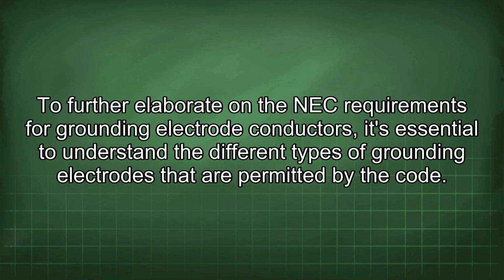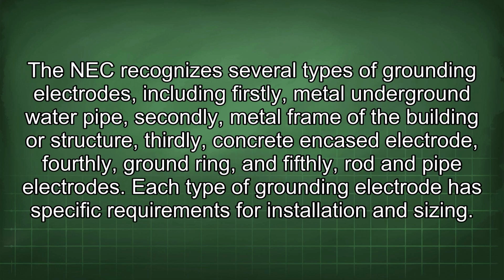To further elaborate on the NEC requirements for grounding electrode conductors, it's essential to understand the different types of grounding electrodes that are permitted by the code. The NEC recognizes several types of grounding electrodes, including firstly, metal underground water pipe, secondly, metal frame of the building or structure, thirdly, concrete encased electrode, fourthly, ground ring, and fifthly, rod and pipe electrodes. Each type of grounding electrode has specific requirements for installation and sizing.